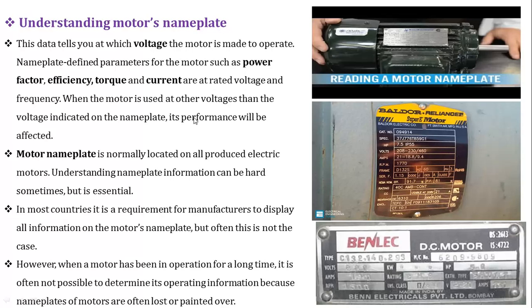When the motor is used at voltages other than the voltage indicated on the nameplate, its performance will be affected. In each and every motor there is a nameplate, and the parameters mentioned there are the operating voltage, the power factor, the efficiency, the torque, the highest rated speed, how much current is required to operate that motor, and the power. So these are some parameters which are already indicated on that nameplate.